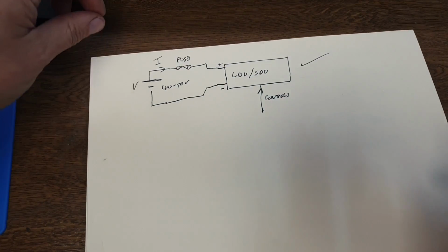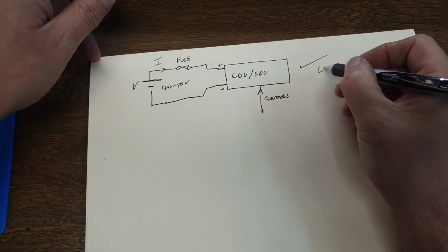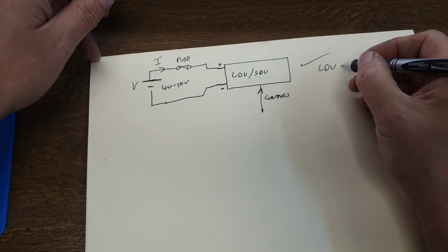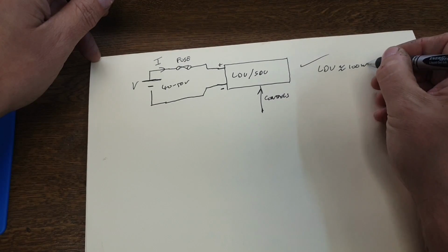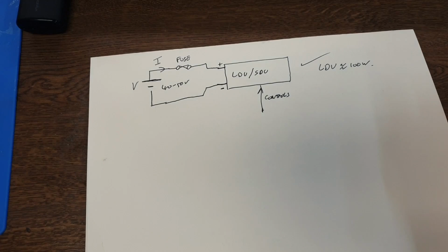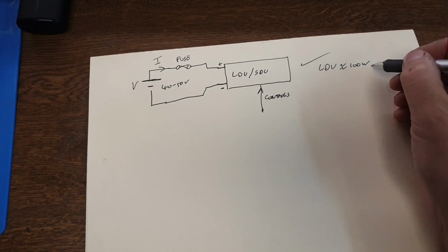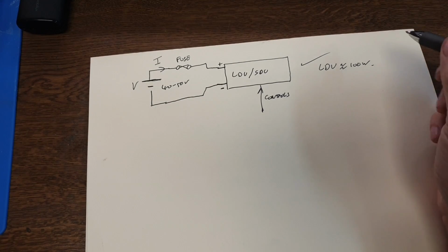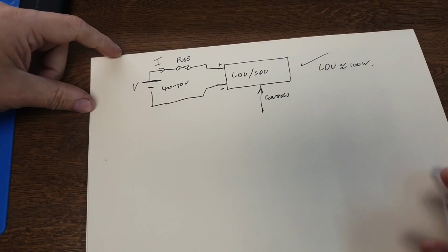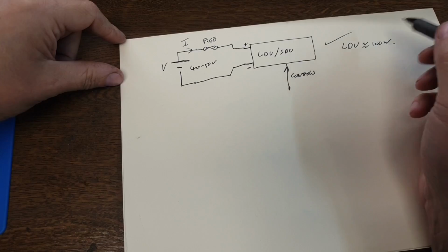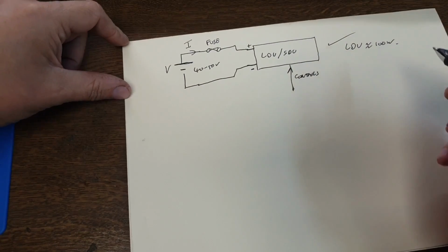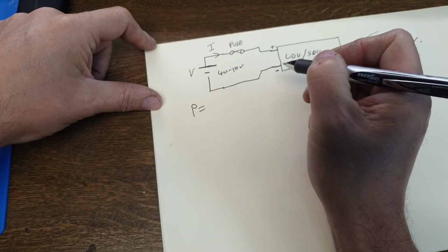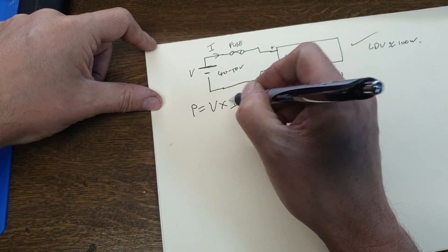One thing to note: to spin the LDU, the bigger of the two motors, takes something around 100 watts of power—not kilowatts or megawatts, just 100 watts, about like an old school 100-watt light bulb used to take. It doesn't take any more than that, assuming there's no mechanical reason for the drive unit not to rotate. Obviously, the faster we want to spin it, the more power it takes. Power, as we know, is voltage multiplied by current.